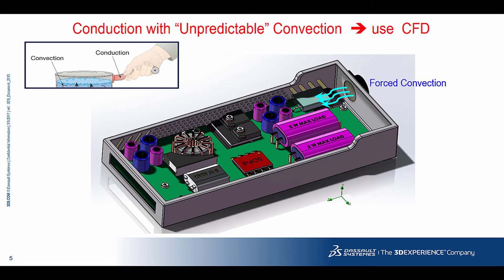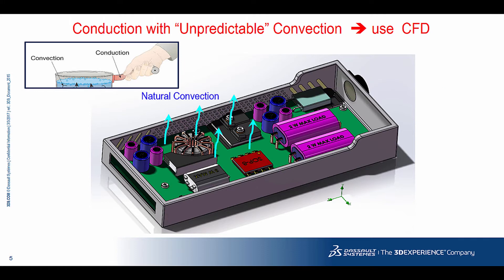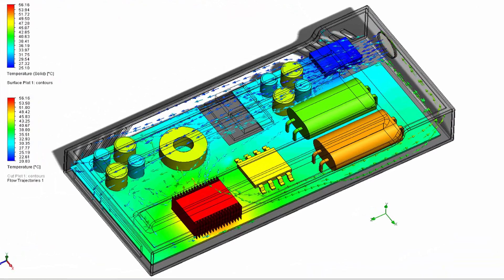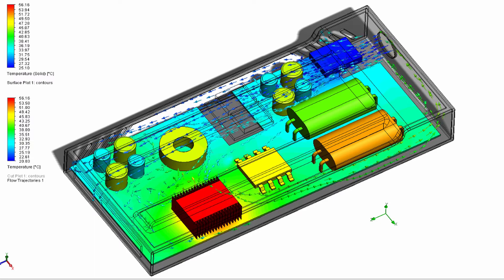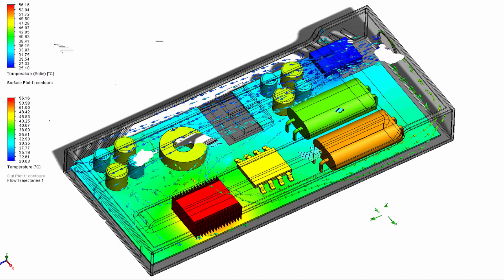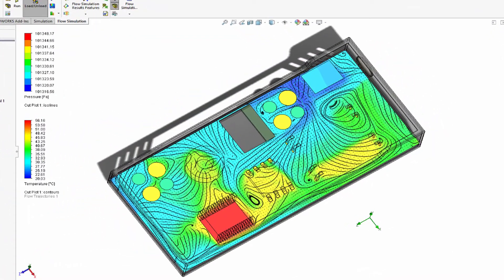Likewise, if buoyancy from natural convection is the primary convection mechanism — for example, your motor has no fan — this system is not predictable, so CFD should also be used, not FEA. Here are the results of the CFD analysis. You can see not only the temperature gradient across the board, but also the dynamics of fluid flow within the enclosure. The streamlined animation and cross-section of the enclosure will help you determine if there is recirculation or areas not getting exposed to forced convection.